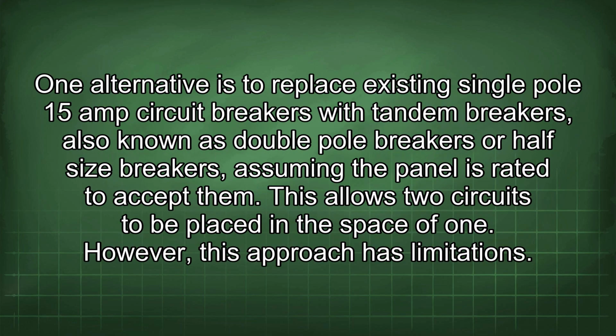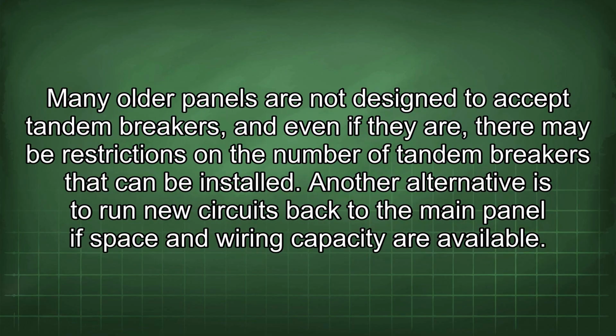subpanel. One alternative is to replace existing single-pole 15-amp circuit breakers with tandem breakers, also known as double-pole breakers or half-size breakers, assuming the panel is rated to accept them. This allows 2 circuits to be placed in the space of one. However, this approach has limitations. Many older panels are not designed to accept tandem breakers, and even if they are, there may be restrictions on the number of tandem breakers that can be installed.